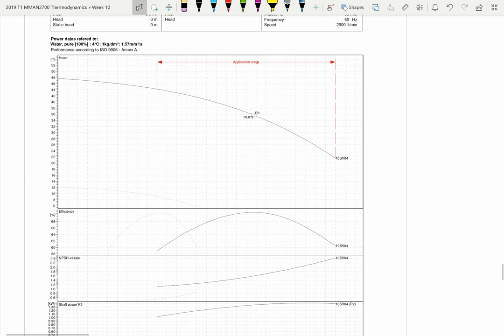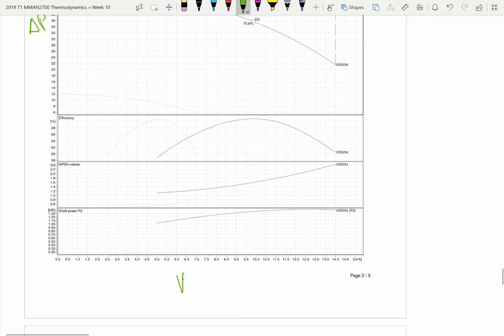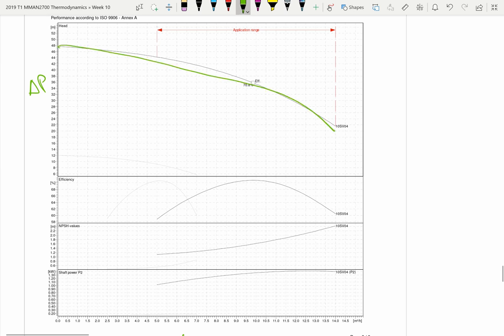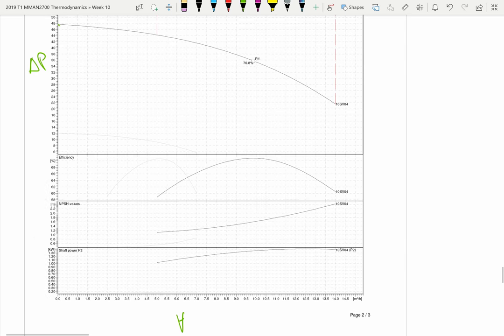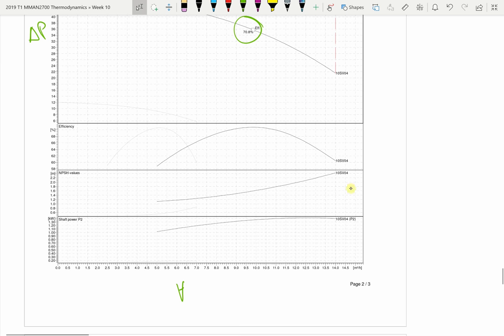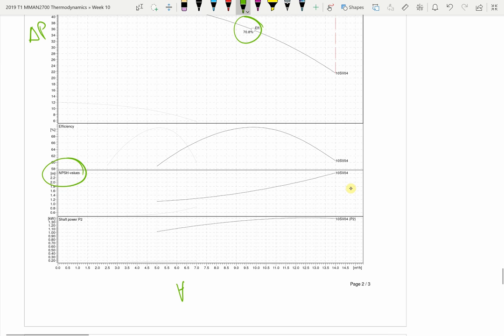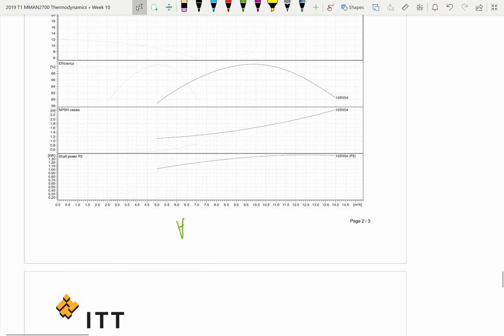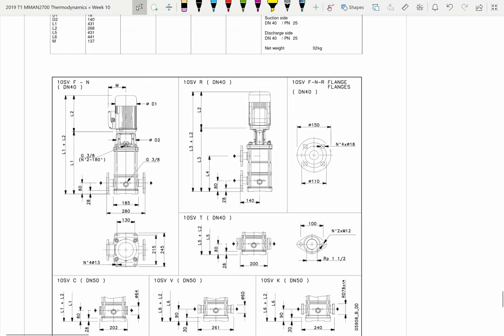This pump has a pump curve as well: ΔP on the vertical axis and volumetric flow rate in metres cubed per hour on the horizontal axis — there's our main pump curve. There's also some other information: efficiency — or isentropic efficiency — with some peak of efficiency and then a drop-off, operating best in a certain range at about 70% efficiency. It also shows how much power is consumed: as you need more volumetric flow rate, you need more power. There's also net positive suction head values, which I won't talk about directly.